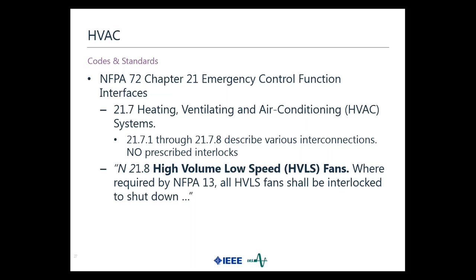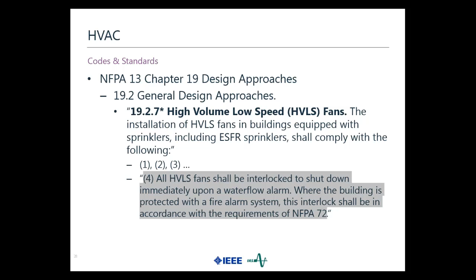The one place that I did find a prescribed interlock was, this is a new section in the 2018-2019 NFPA 72, as 21.8, and it refers to NFPA 13. So I actually went and found the corresponding portion in 13, and here it is. All HVLS, high volume, low speed fans shall be interlocked, shut down upon a water flow alarm. That's the only place I could find where there was actually a prescribed interlock for an HVAC system based on any kind of fire protection.